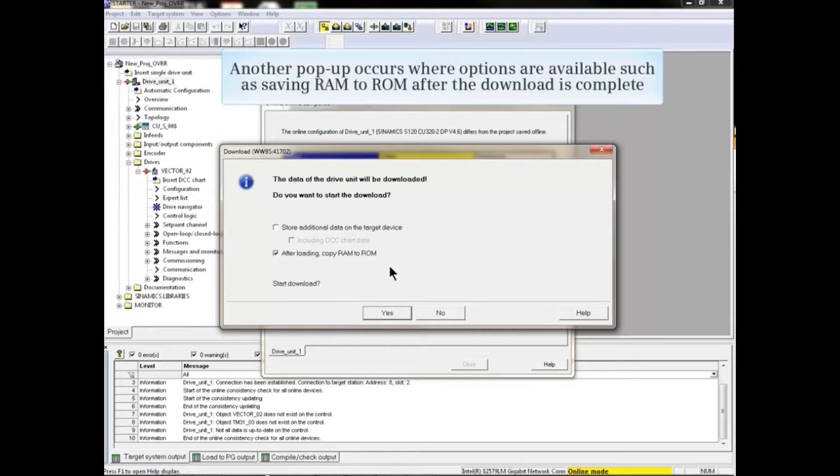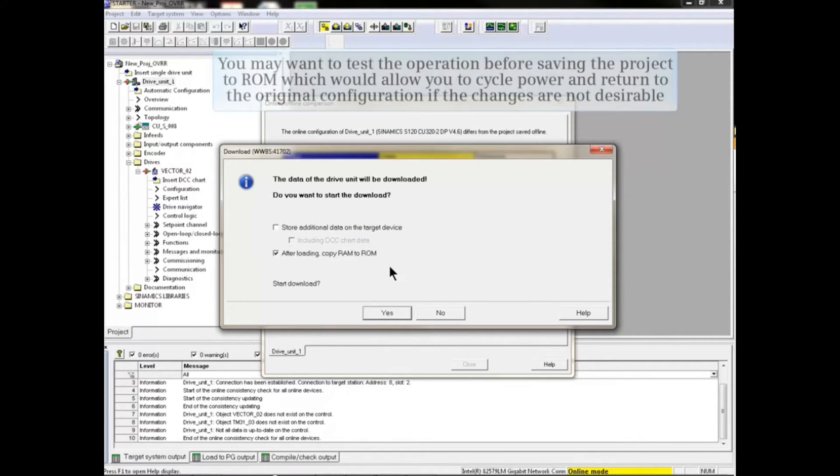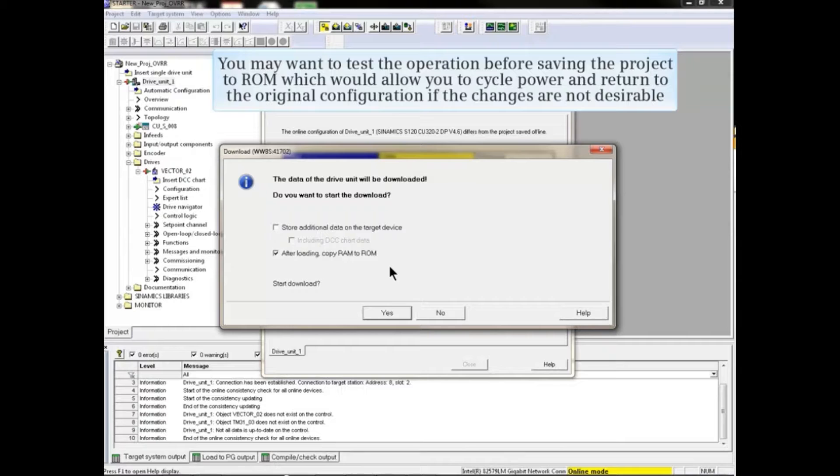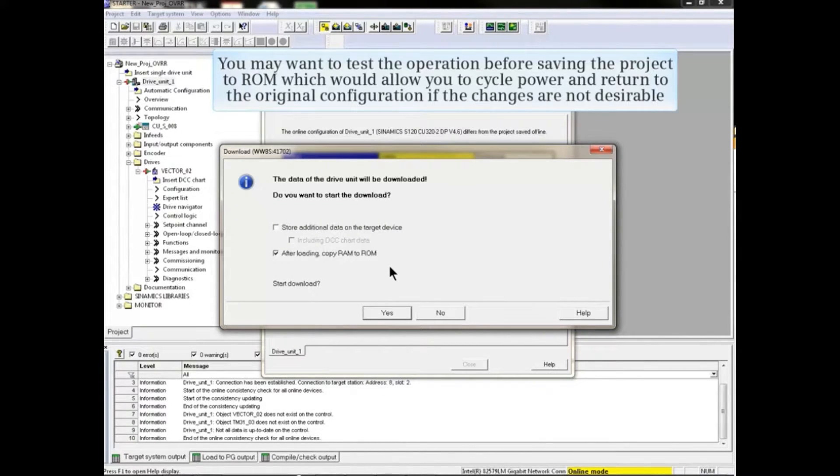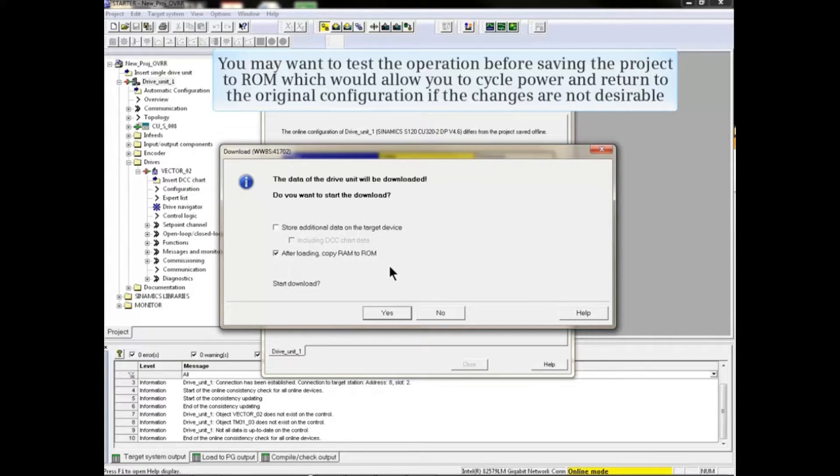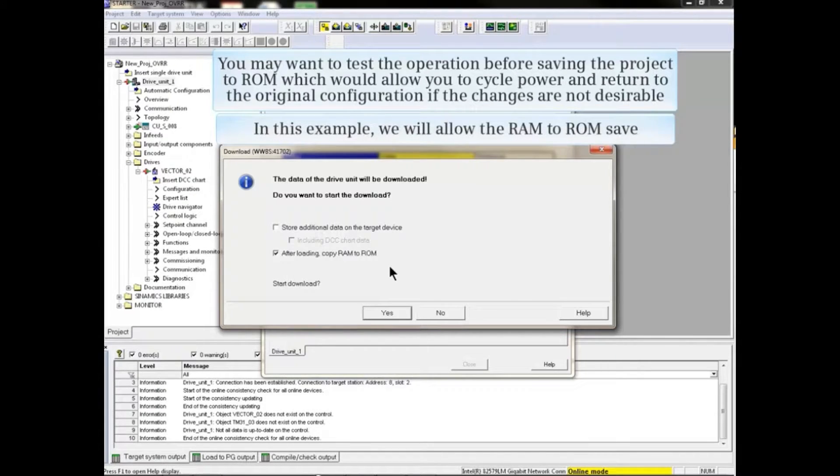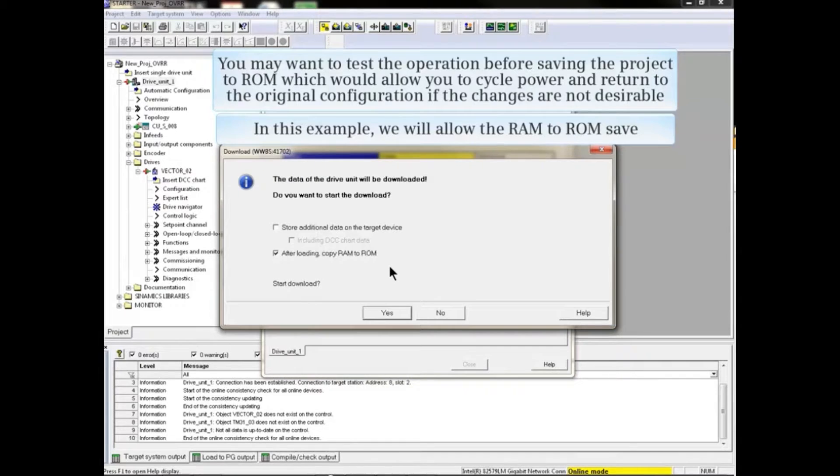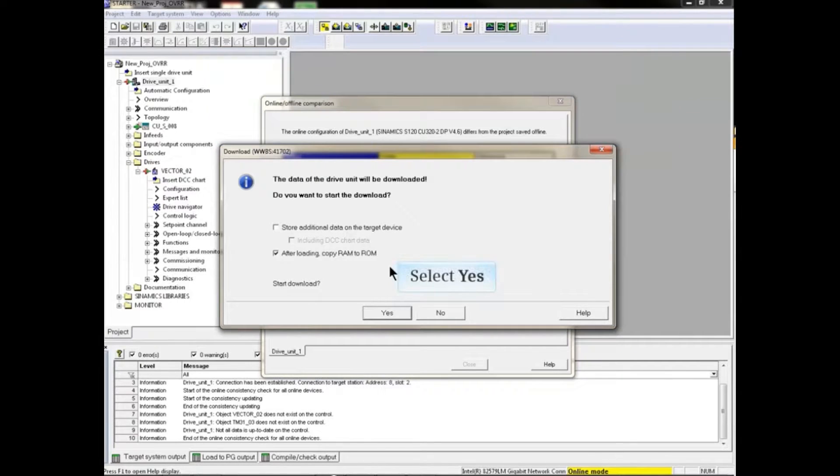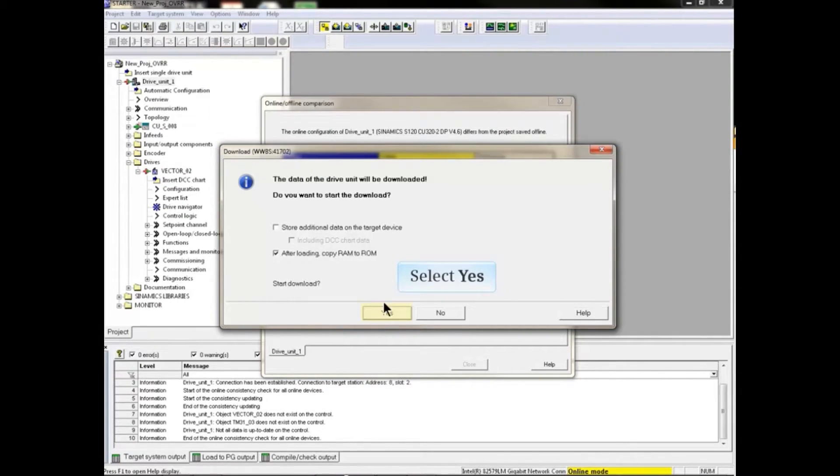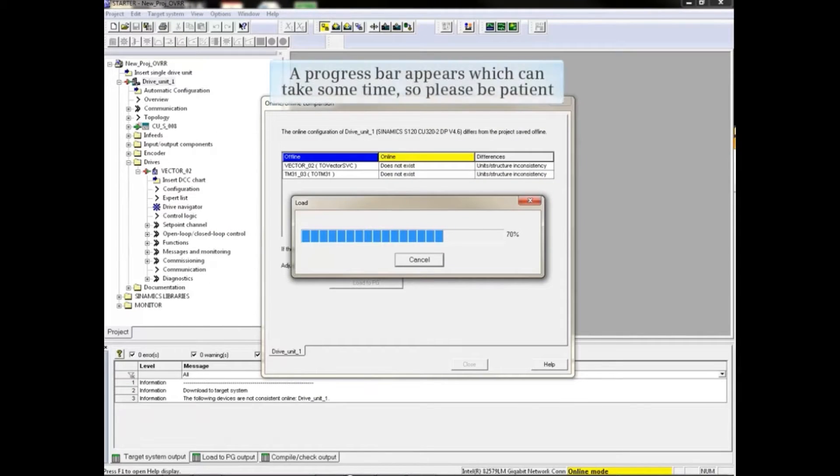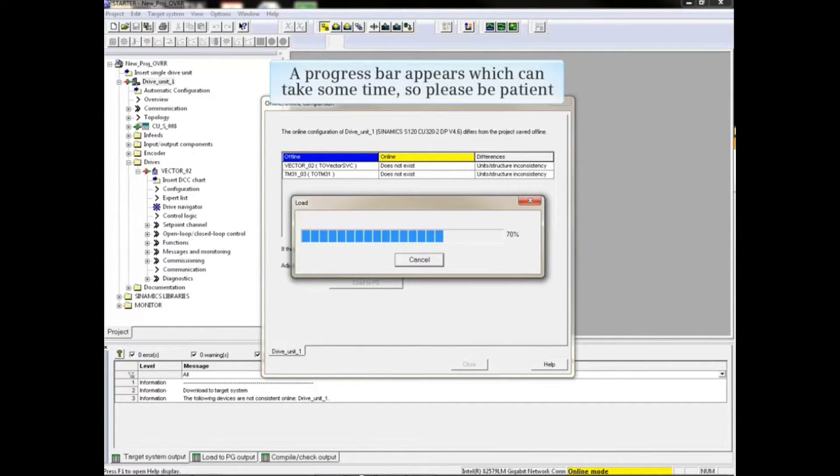After the download is complete, you may want to test the operation before saving the project to ROM, which would allow you to cycle power and return to the original configuration if the changes are not desirable. In this example, we will allow the RAM to ROM save. Click yes to initiate the download. A progress bar appears. This can take some time, so please be patient.